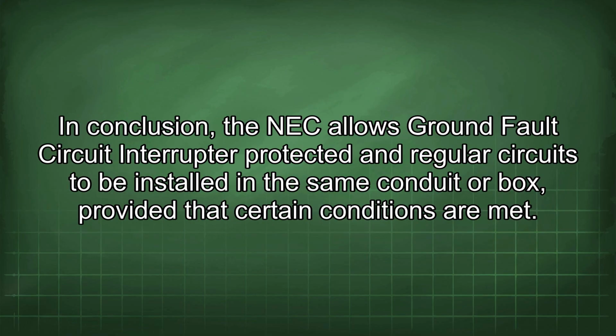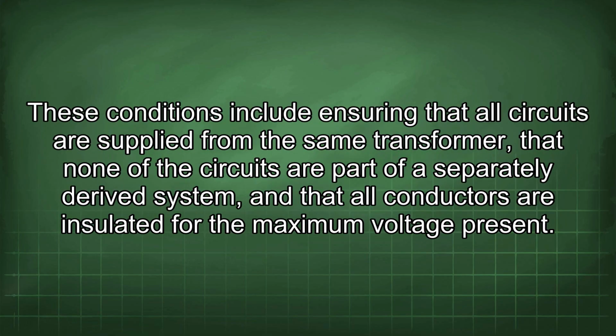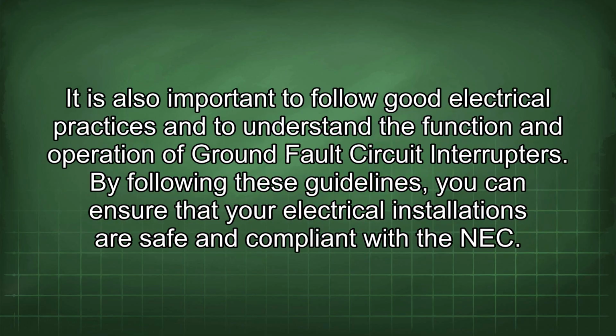In conclusion, the NEC allows ground fault circuit interrupter protected and regular circuits to be installed in the same conduit or box, provided that certain conditions are met. These conditions include ensuring that all circuits are supplied from the same transformer, that none of the circuits are part of a separately derived system, and that all conductors are insulated for the maximum voltage present. It is also important to follow good electrical practices and to understand the function and operation of ground fault circuit interrupters. By following these guidelines, you can ensure that your electrical installations are safe and compliant with the NEC.